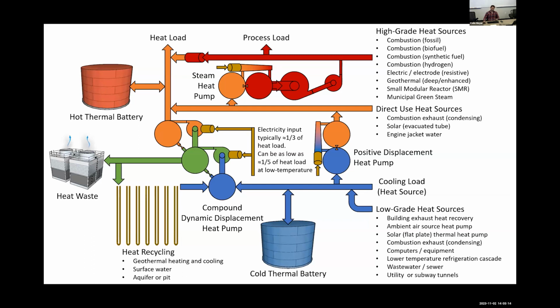These are false cooling loads that increase the load on the chilled water system when they're dispatched. You would dispatch them selectively to provide more source to the district heat pump. And then those low-grade heat sources can be converted to useful heating temperatures through the heat pump. And so that's why we use that term heat pump, because it's no longer just a chiller. It is doing some beneficial cooling, and it is chilling water to achieve its intended purpose. But we start to call it a heat pump just because it's really just moving heat from one temperature to another. Where that heat came from may have been a cooling load, or it may have been another source of low-grade heat. Just wanted to get on the same page with some definitions there.